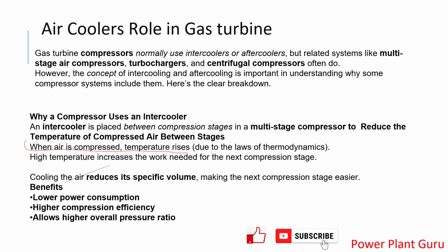Now, why do we need to cool that air before the next stage starts? There are two or three benefits. One is that cooling reduces the specific volume, so the next stage of compression is easier and you get lower power consumption in the next stage.